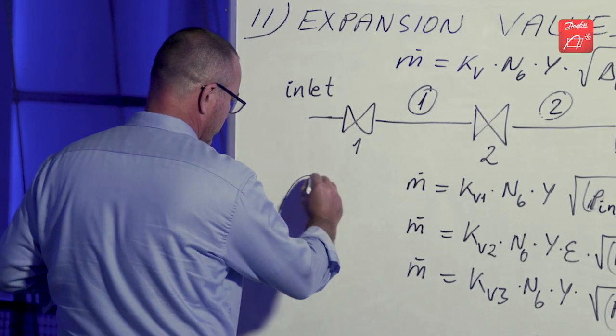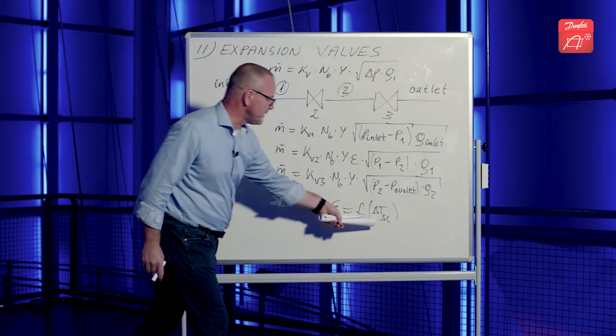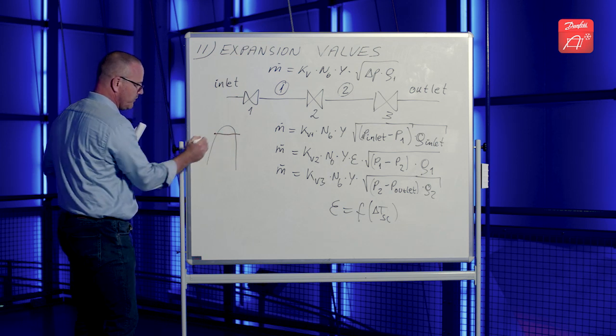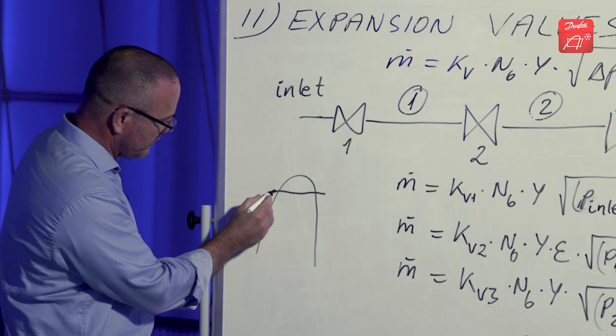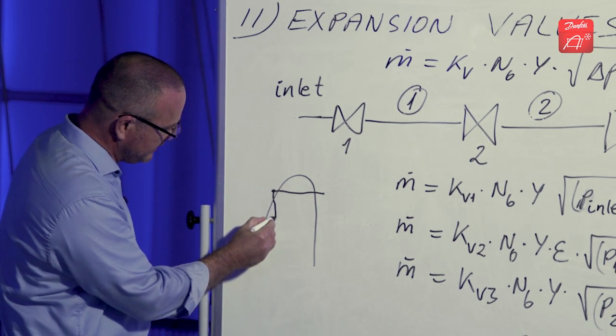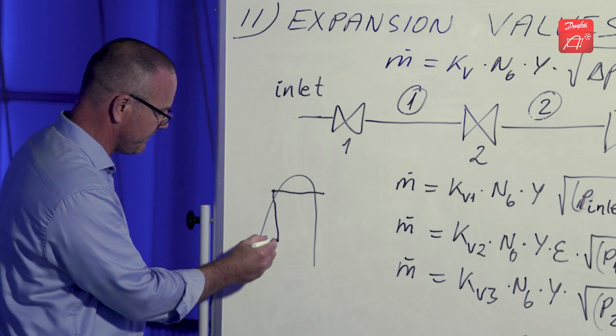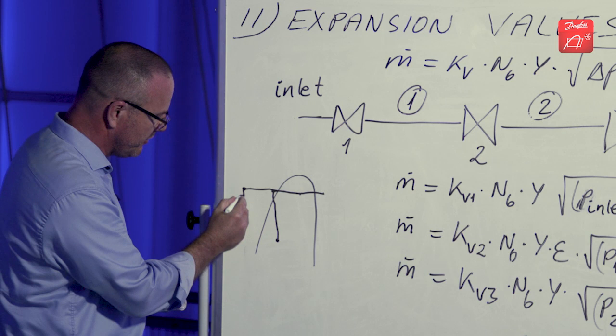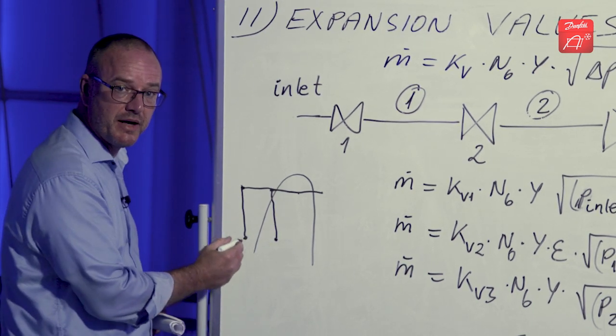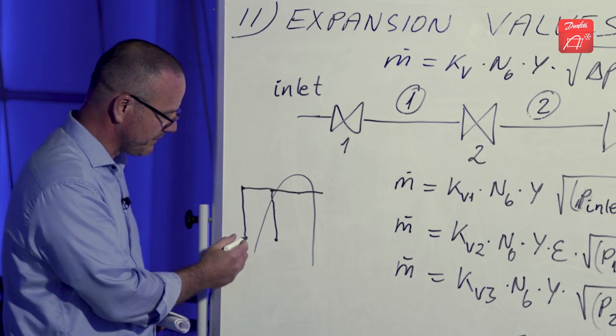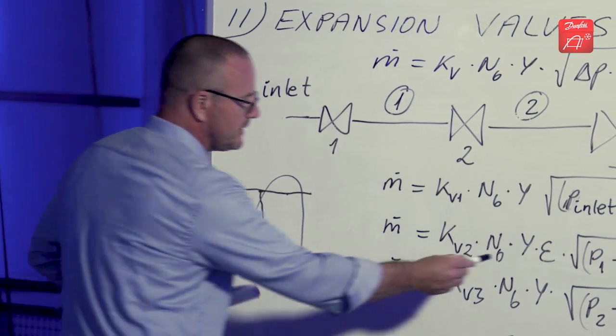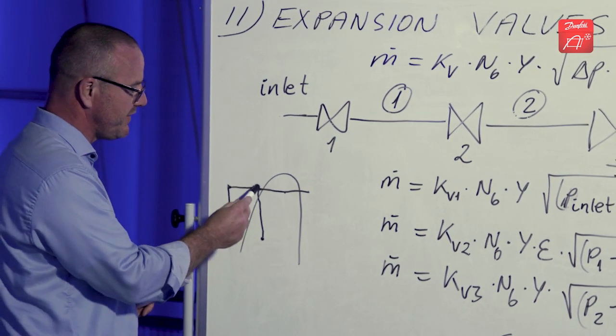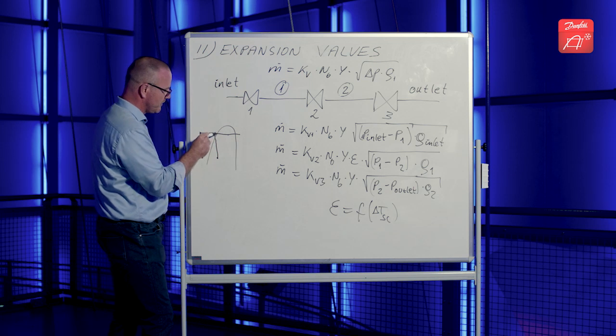Now, the reason we correct this equation set with the subcooling is that if you start with a very low subcooling for the expansion valve, you start out by immediately expanding into the two-phase area. On the other hand, if you have a very large subcooling, you can actually end up in a situation where you're just expanding out of the liquid area all the time. So, this epsilon has a value of 1 for very large subcooling and it has a value less than 1 for very low subcooling.